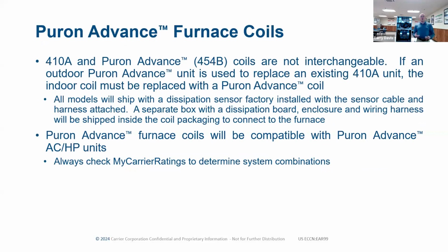I've said this before, 410A and 454B components, coils, they're not interchangeable. You can't use a 454B coil on a 410A system and vice versa. Can't use a 410A coil on a 454B system. If you're doing a change out on a split system, like I said, if you are just changing the outdoor unit, you can go back with a 410A outdoor unit. If you're just changing the indoor coil, you can go back with a 410A coil if it was originally 410A. But if you're going with a new 454B unit, you've got to go indoor and outdoor.